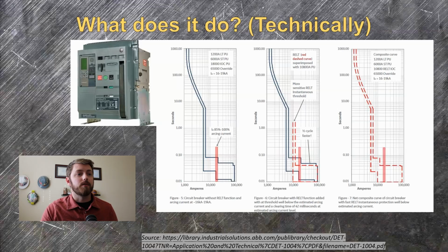Let's take the following breaker for example. Under normal conditions, for this 1200 amp breaker, the settings will be long time 1 times 1200 amps, 1200 amp frame rating, with a 6-second delay. Short time is set to 5, which would be a 6,000 amp pickup with a 0.06 second delay. Instantaneous is set to 15, that's 18,000 amps. And then our RELT setting, our reduced energy let-through maintenance mode setting, is going to be 9, which is 10,800 amps. So with maintenance mode or RELT disabled, the instantaneous trip is 18,000 amps.